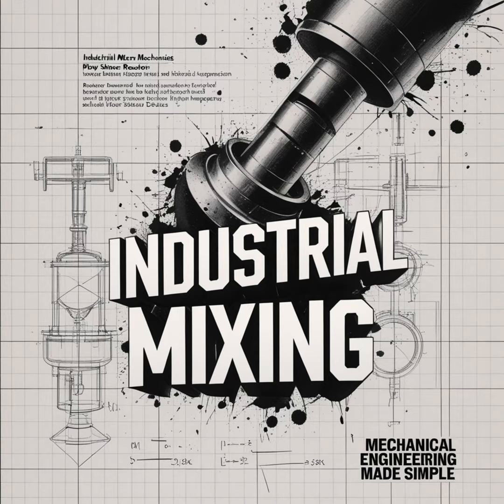And placement matters too. Where do these gauges actually go? If you're just measuring the total power draw, a single gauge set can be placed high on the shaft, above the liquid level. But if you're doing detailed process optimization, especially in a system with multiple impellers— Say one near the top and one near the bottom. Exactly. Maybe a feed impeller near the top and a gas-dispersing impeller at the bottom. In that case, you need multiple gauges. They're positioned strategically to measure the torque contributions from each individual impeller, which lets you understand how much power is being consumed in different parts of the tank. That deeper understanding of localized power is key.